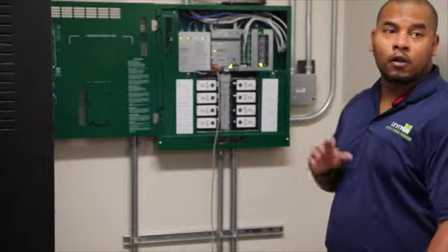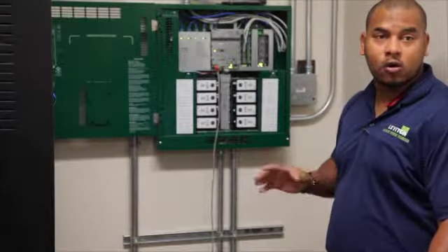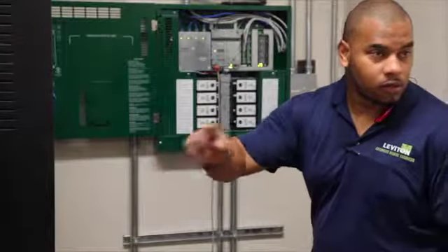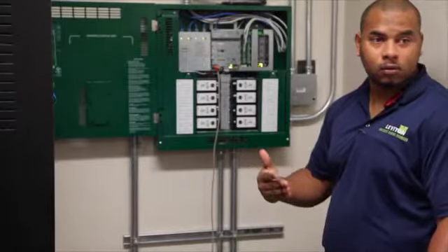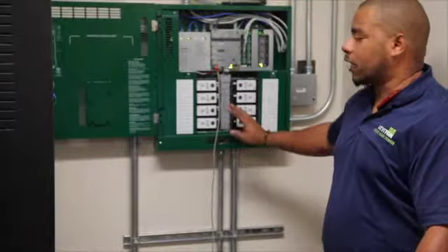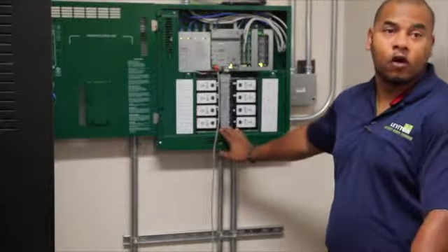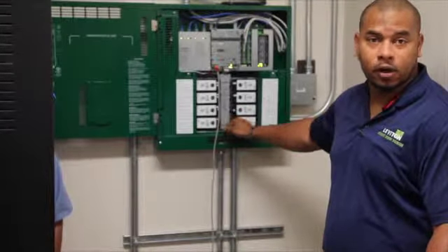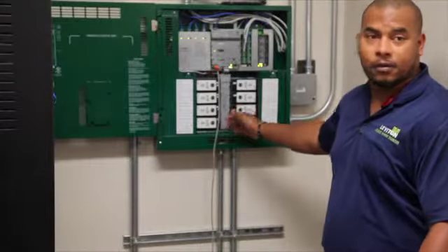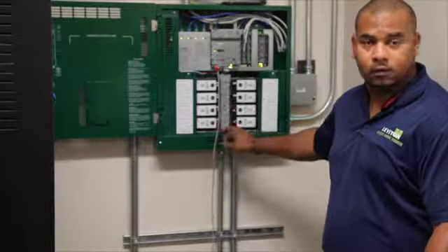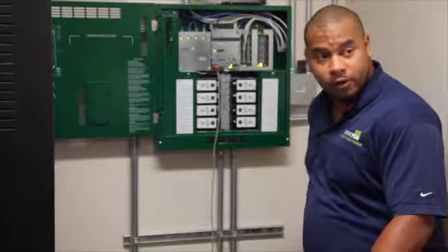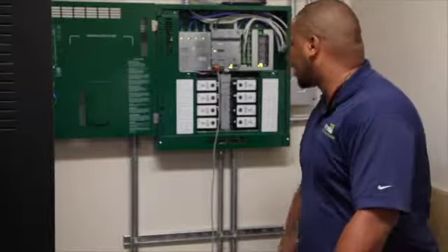Now, in other areas where you have digital switches that control relays, you can override the manual relay by just pressing the digital switch to change the action. But your exterior lights do not have an override associated with them. So you have to be mindful that if you turn it on or you turn it off, you have to come back and turn it off or on again. Are they labeled here as well? Yes. Which ones are exterior? Yes. They're also labeled which ones are emergency as well. Okay.